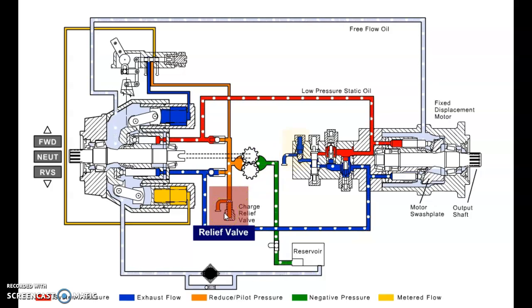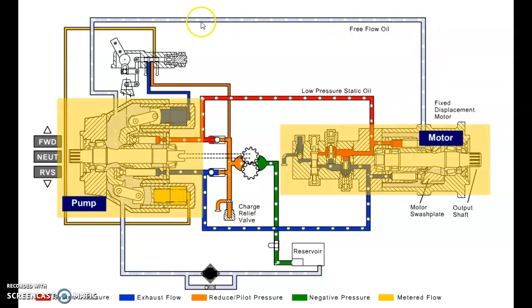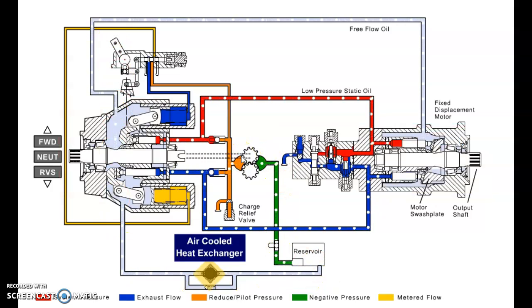Not the neutral charge relief, but the flushing relief or operating charge relief, which is generally set 10 or 20 psi lower than the neutral charge relief. And that's dumping the oil into the motor case, going out the case drain line to the pump case, back to the reservoir. The charge pump is going to pick it up and keep putting it back in at pressure.